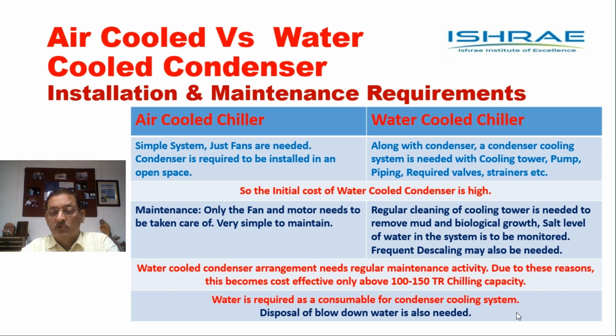In addition, frequent descaling may also be needed, because of the salt content, scaling can take place in the condenser pipes. So frequent descaling would also mean a reduction in the life of the condenser. Water-cooled condenser arrangement needs regular maintenance activity. Due to these reasons, this becomes cost-effective only above 100 to 150 TR chilling capacity. At lower chilling capacity, below 150 or 100 TR, normally in most places, the water-cooled condenser or water-cooled systems are not cost-effective as compared to air-cooled systems.